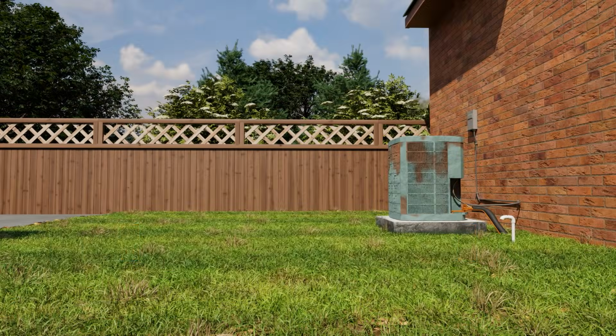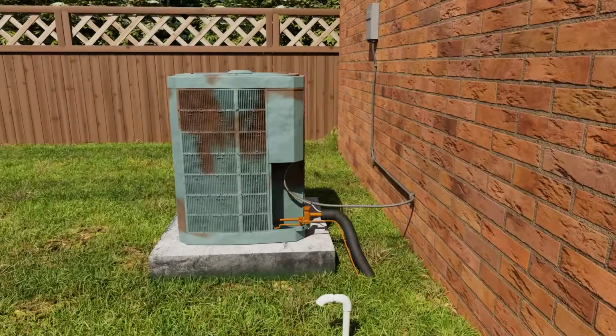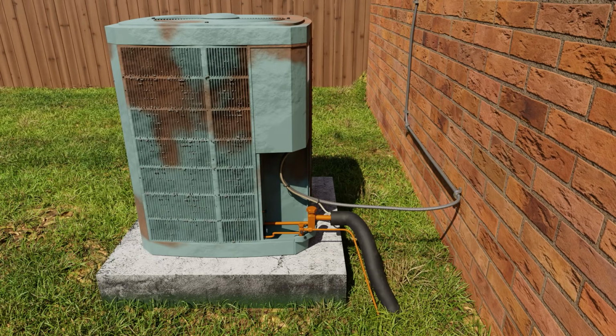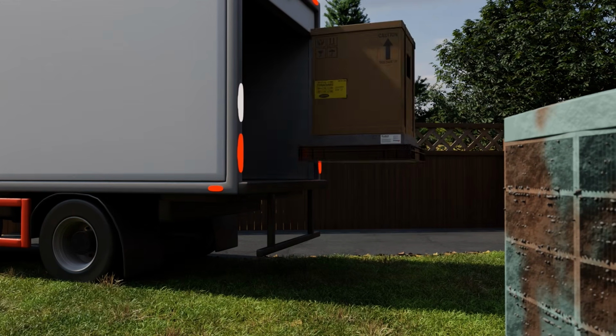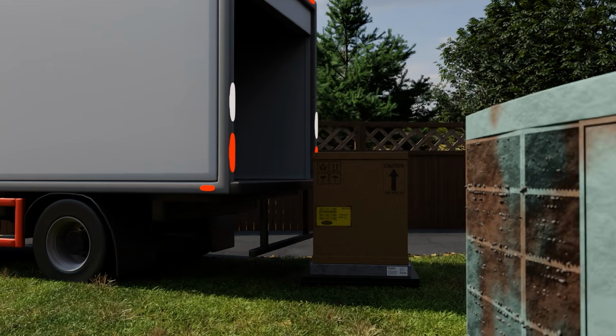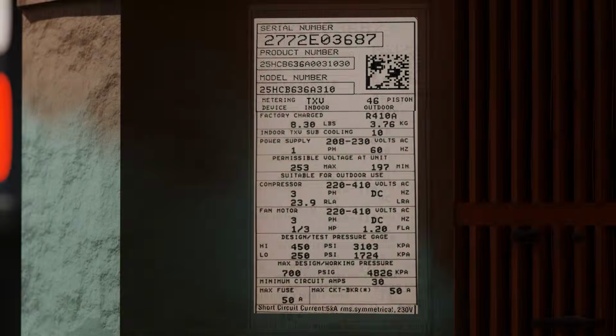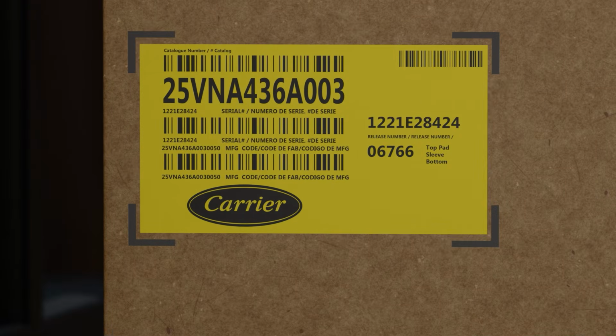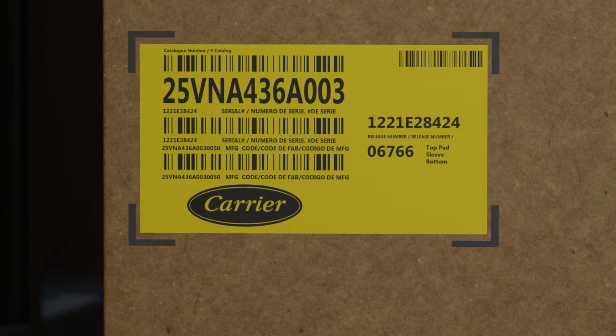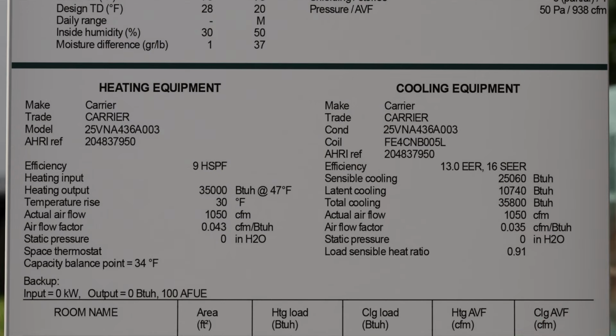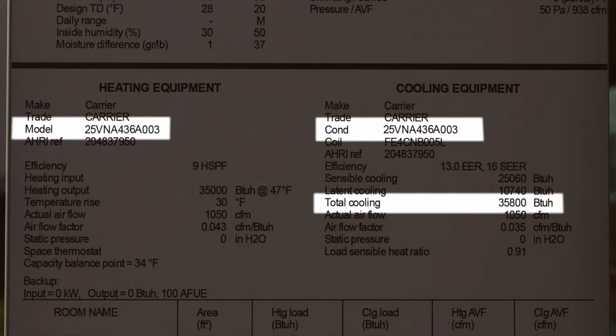Once you get to the site, the first thing you want to do is identify the application. Check to see if you'll be replacing the concrete pad or not. Safely unload the condenser, then confirm that it's a match for the replacement unit. The 36 in the model number means these are both 3-ton units, because it's 12,000 BTUs per ton. Check that the tonnage is correct by looking at the manual S and manual J calculations for the job.